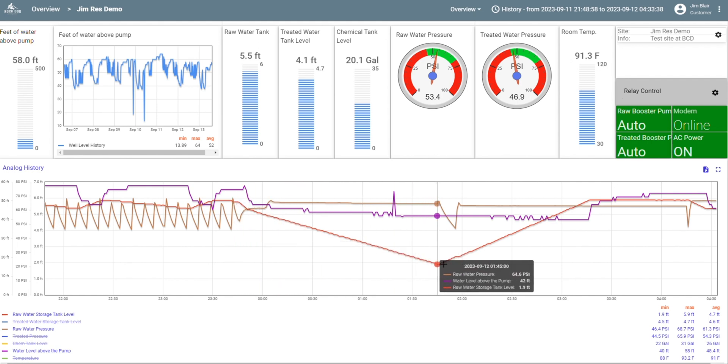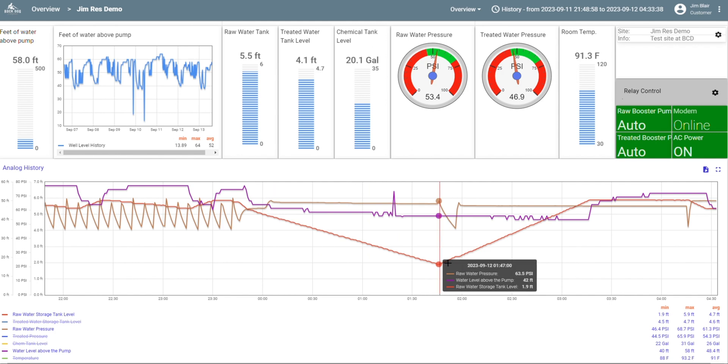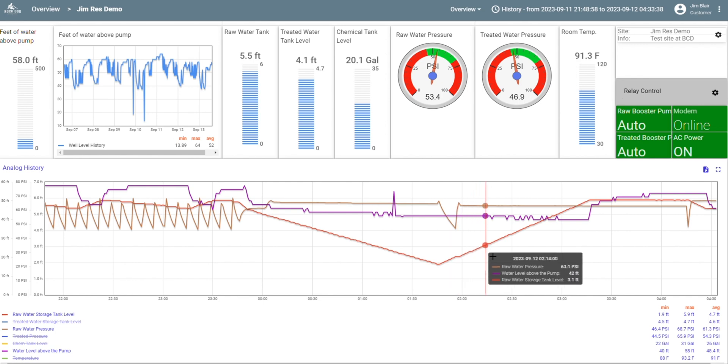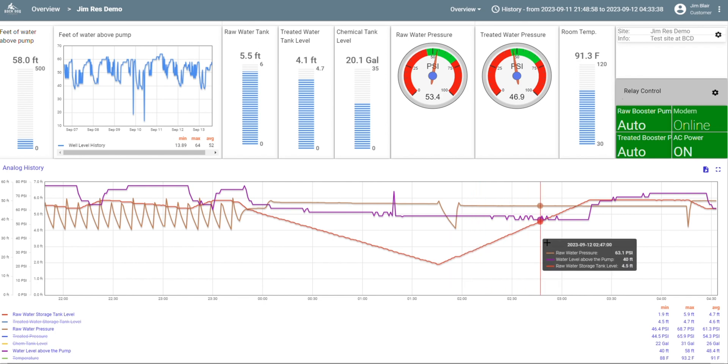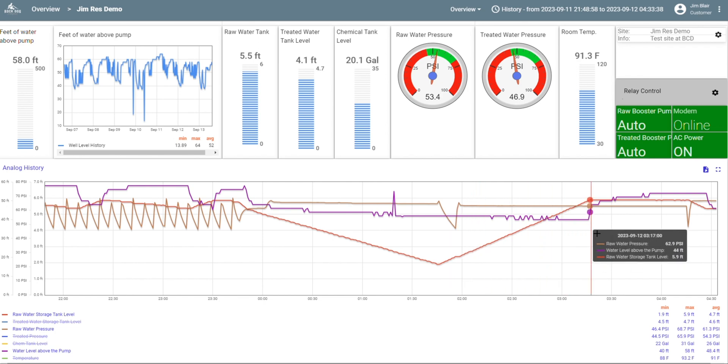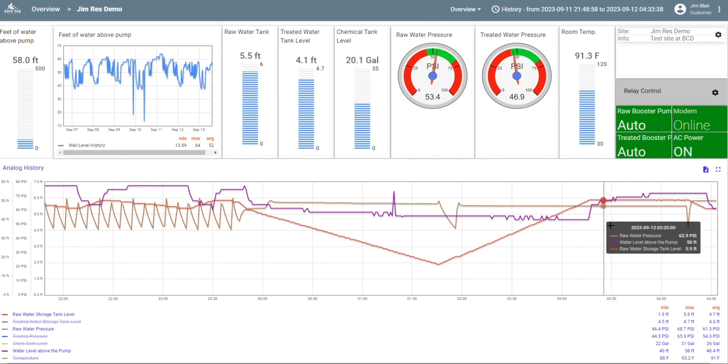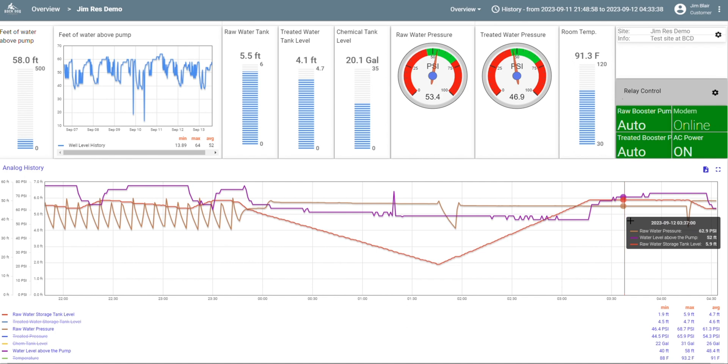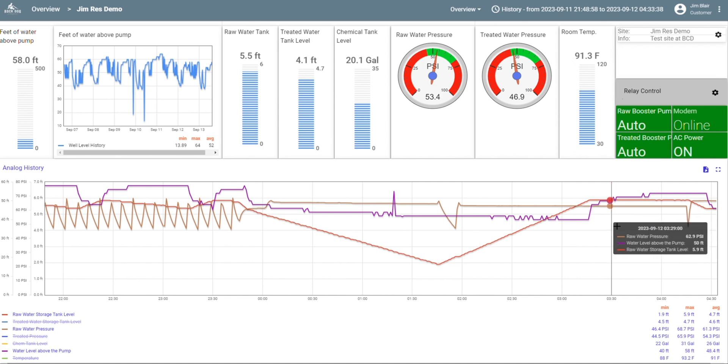At that point, the irrigation system was done for the night and the storage tank recovered as the well kept filling it. And it got the tank full about 3:15 in the morning. Now the well pump cut off and you see the purple there, that's the water level in the well, you can see the well recovered immediately. It's pretty cool to see all of this data in one place. And if you have a problem, you can pinpoint that right away.